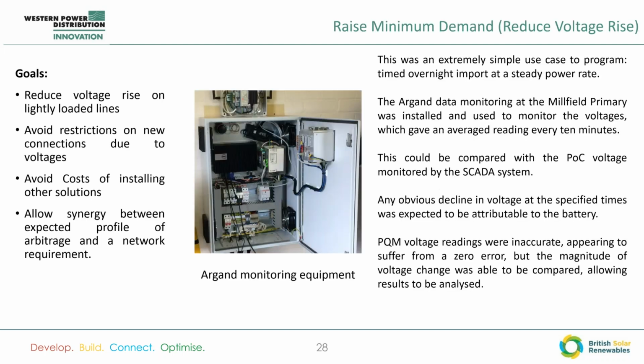Right. Our next use case is raising minimum demand or reducing voltage rise. And you've got those the wrong way around. Simple use case. You just import the power overnight to increase the minimum demand and reduce the voltage rise. So again, we wanted our Argand's information on this. That's why we had the monitoring installed, because we thought we could see a significant change of voltage at the POC, but by the time it runs down the kilometres of 11 kV feeder, it might not have any real impact back at the primary.